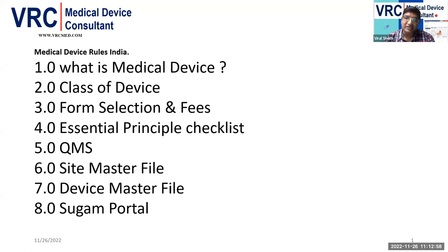That is covered in the essential principle checklist. If you are a manufacturer or importer, your system must meet the quality management system requirement specified in Schedule 5 of the Medical Device Rules. That is almost similar to ISO 13485, which is the quality management system requirement for medical device manufacturers.